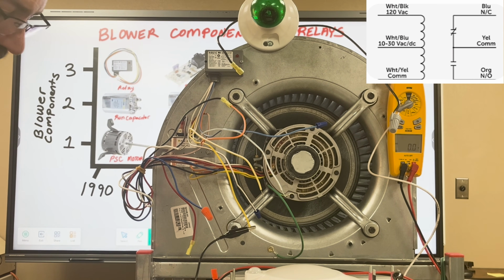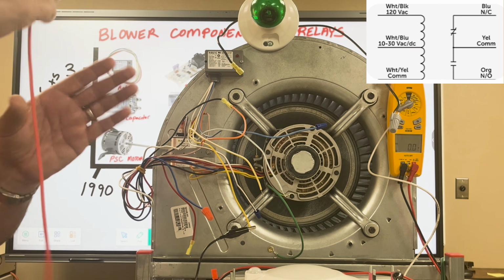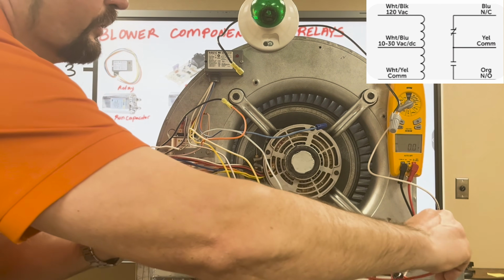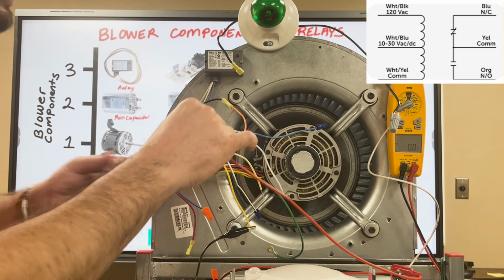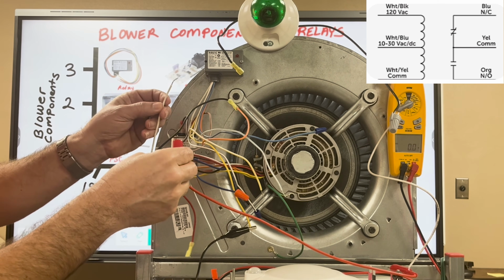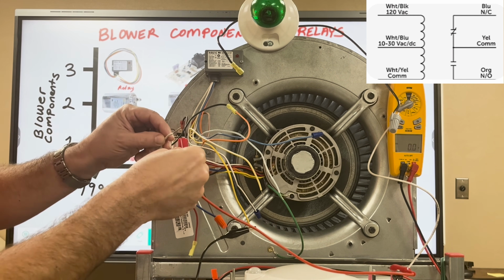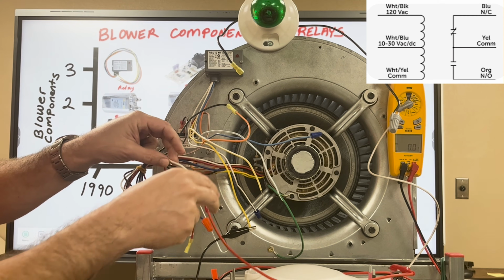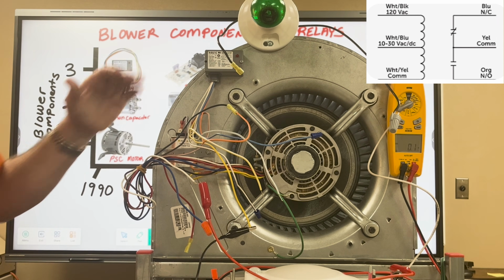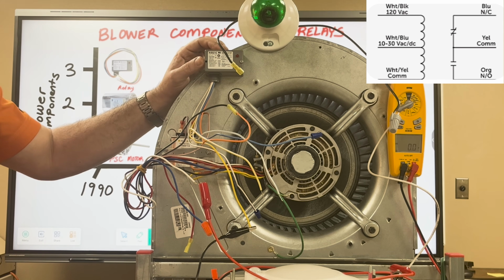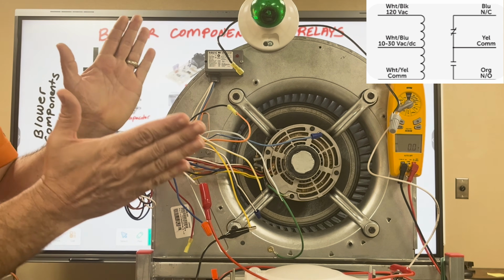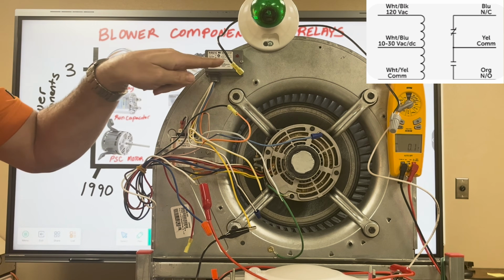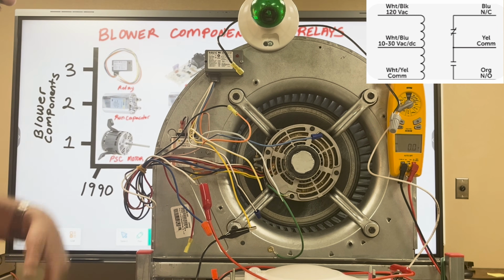We're going to go ahead and wire up the other side of the fan motor. I'm going to go ahead and use red for our other line voltage. And that's going to go to the white wire on the motor. Okay. And now the moment I give my coil, my RIB relay, 24 volts, the contacts will close. You'll obviously see a red light and the motor will come on and run.